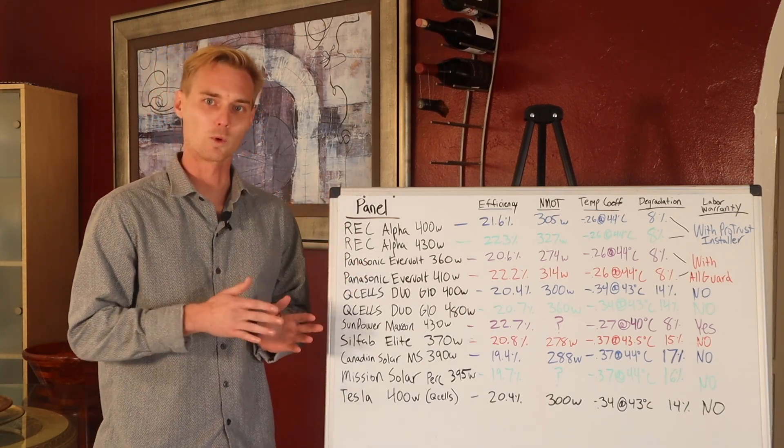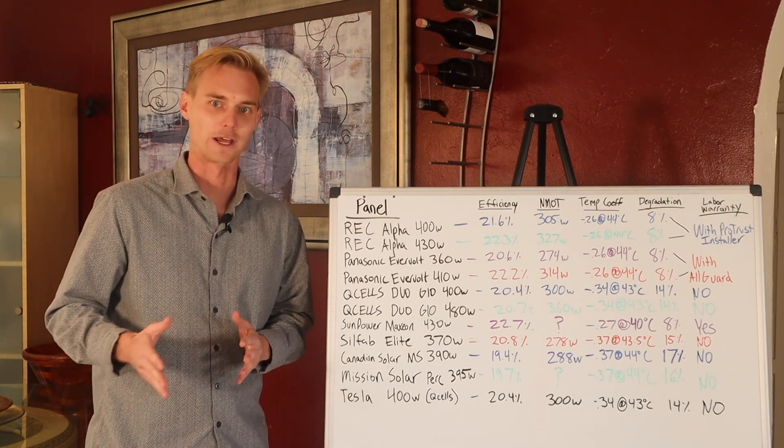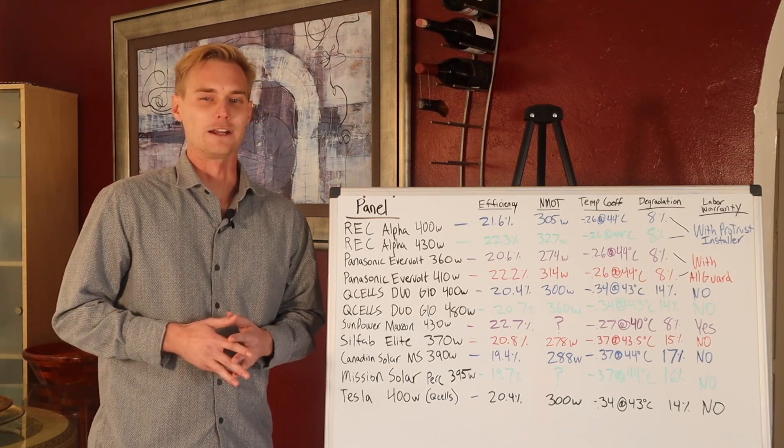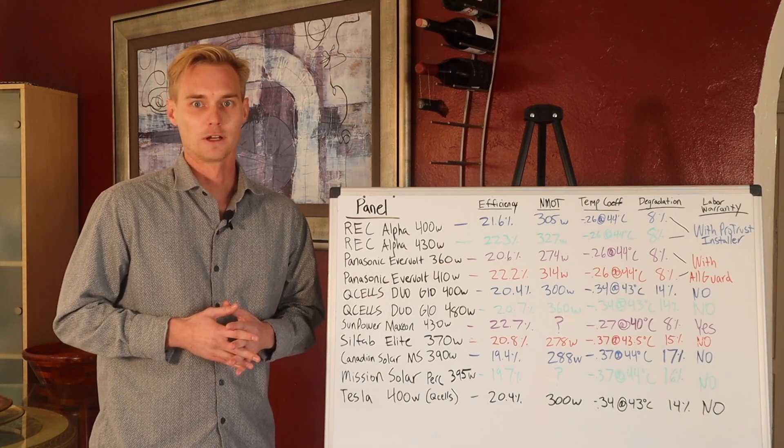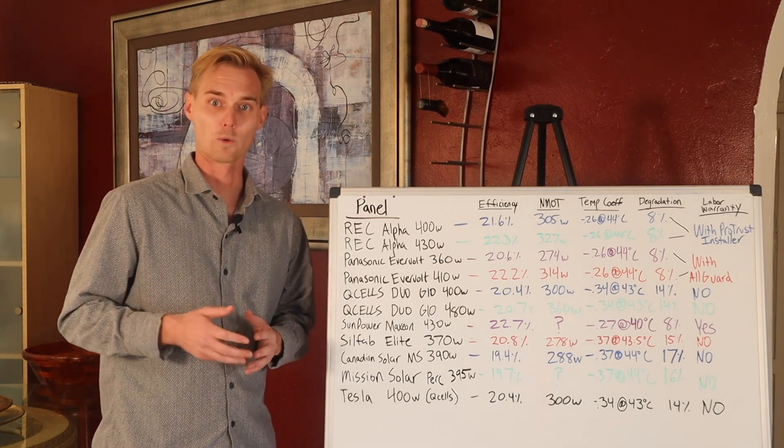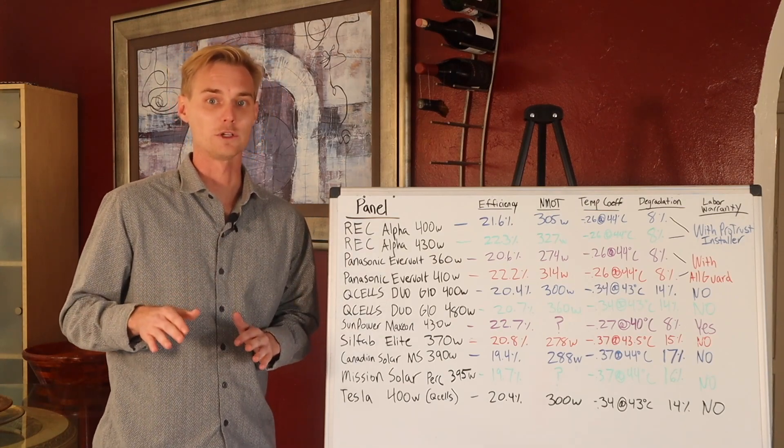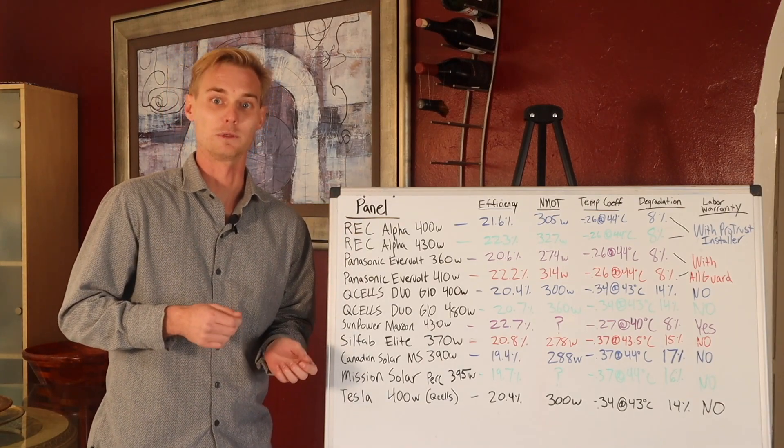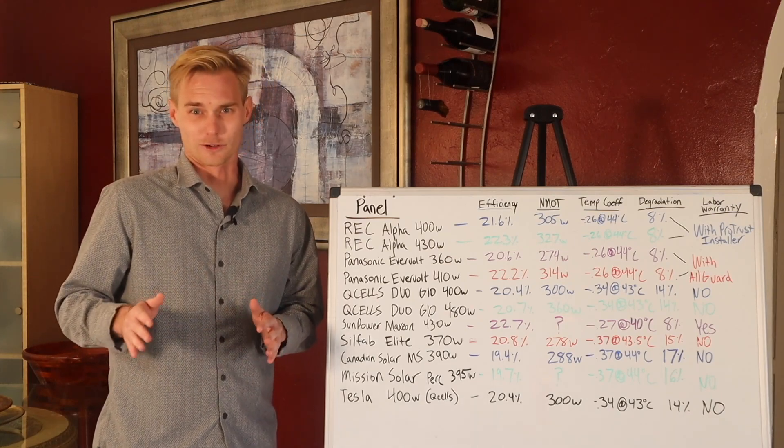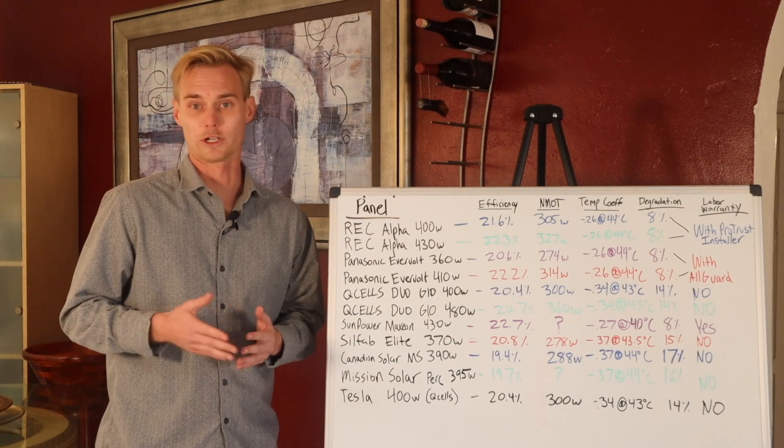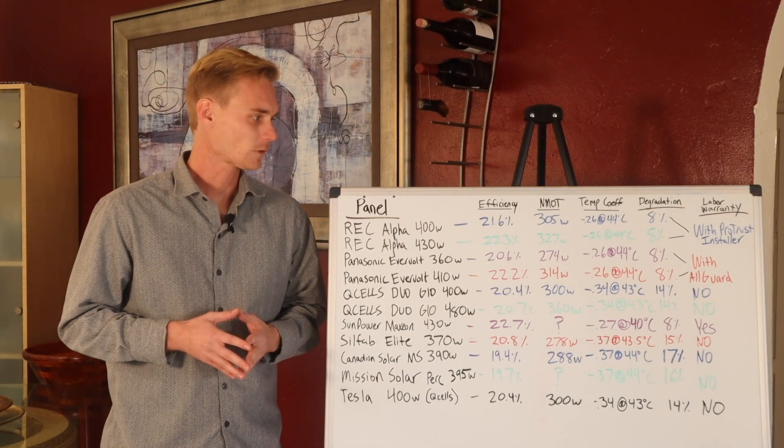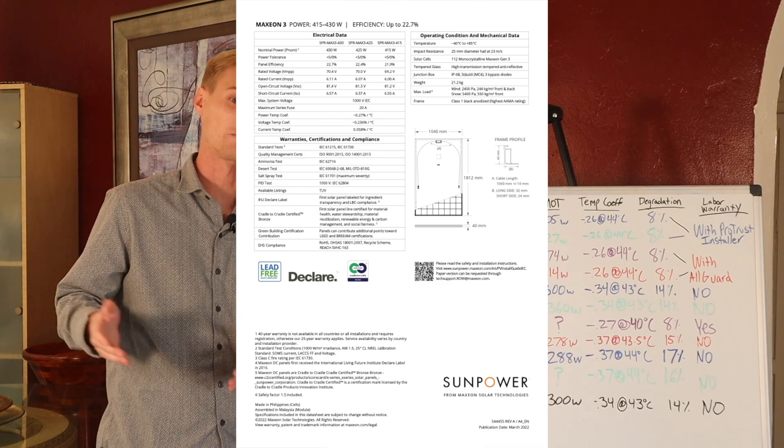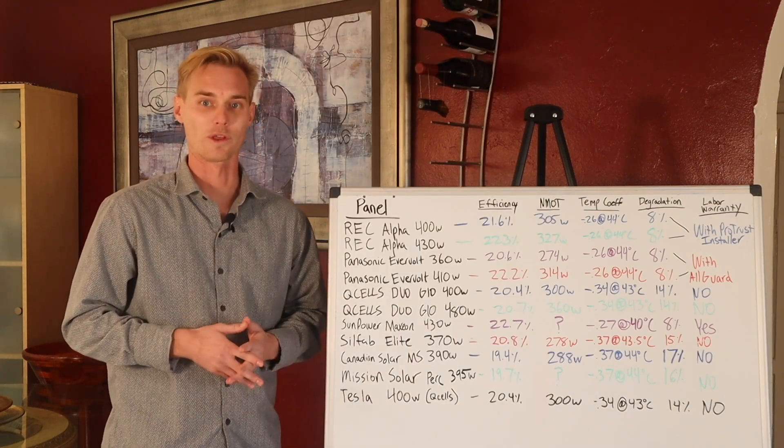The efficiency is the number one most important rating you need to understand. The general rule of thumb is anything over 20% is going to be considered really good. Anything under 20% is kind of mediocre nowadays. Some panels are even over 21%, even over 22%, and those are your super premium modules. The Panasonic, RECs, and Sunpowers are the most efficient panels on the market.